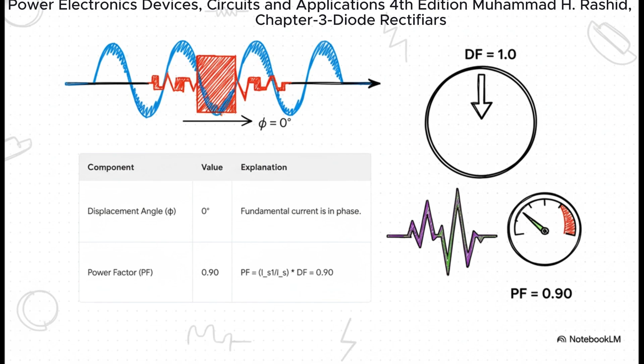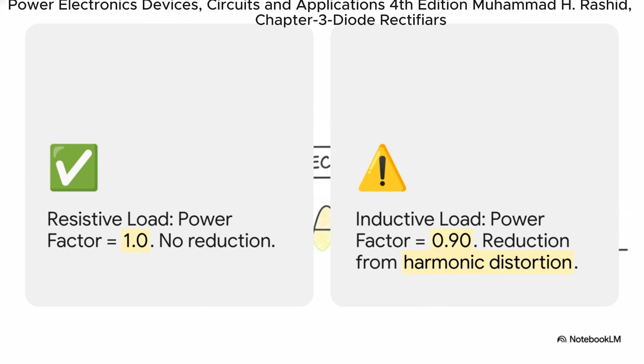For that simple resistive load, you get a perfect power factor of 1.0. For a rectifier driving a motor, it drops to 0.9. And the entire reason for that drop is the harmonic distortion. It wasn't a phase shift problem, it was a shape problem. The waveform itself was the culprit.